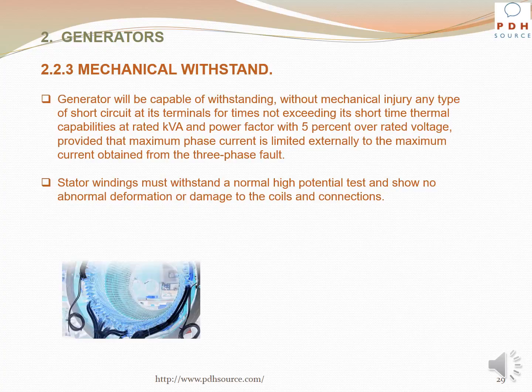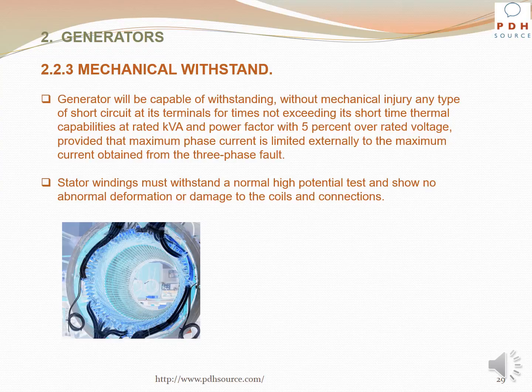Generator will be capable of withstanding without mechanical injury any type of short circuit at its terminals for times not exceeding its short time thermal capabilities at rated kVA and power factor with 5% over rated voltage, provided that maximum phase current is limited externally to the maximum current obtained from the three-phase fault. Stator windings must withstand a normal high potential test and show no abnormal deformation or damage to the coils and connections.